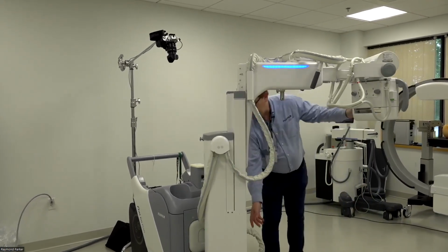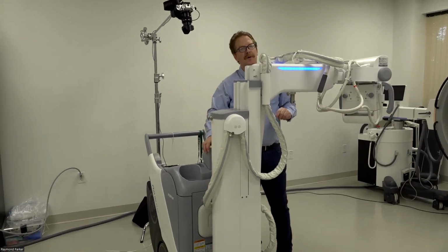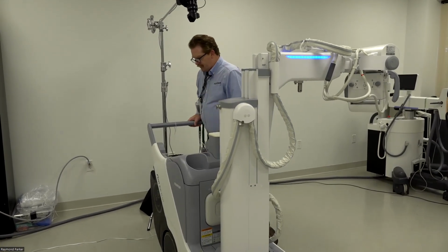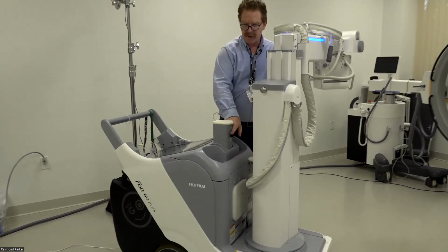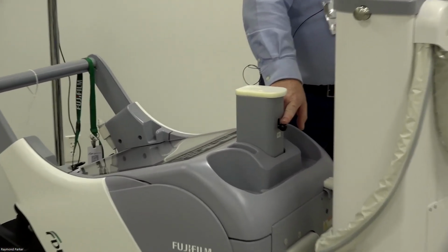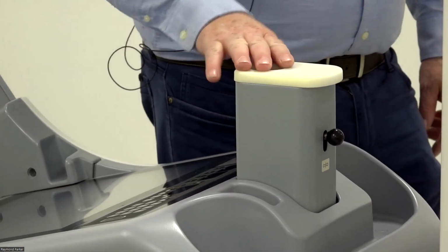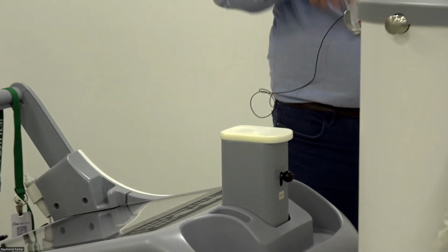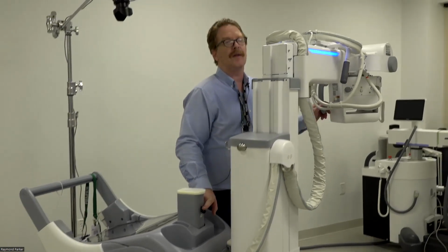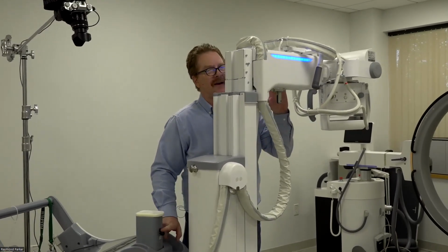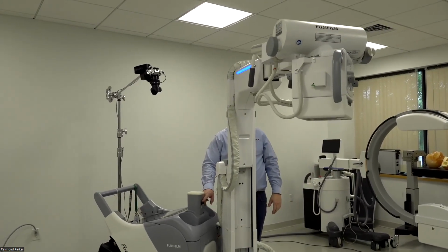One of my favorite lock releases to show, especially at sites that have had our portable, is this lock release right here. This lock release is not only to remove or allow it to leave the cradle. That's what most people think. It is actually an all lock release, and when it is activated, it allows you to swing the tube and have all locks released.